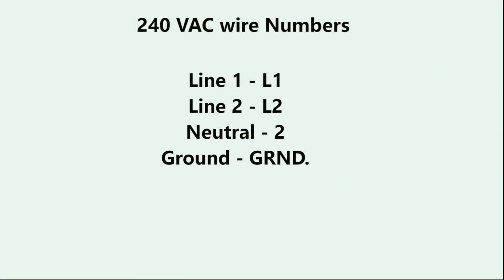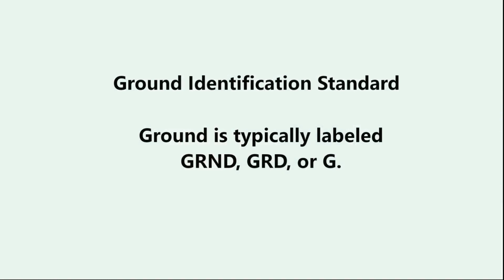Sometimes we're going to use 240 volt AC. If we do that, we come up with these names. Line 1 is L1, line 2 is L2, neutral, if there is one, is labeled 2, and ground is labeled GRND. Many times ground is not labeled because green is universally known as the ground wire. However, if you do label the ground wire, it will be GRND, GRD, or G. And it will let you know that this is a ground wire and it is safe.